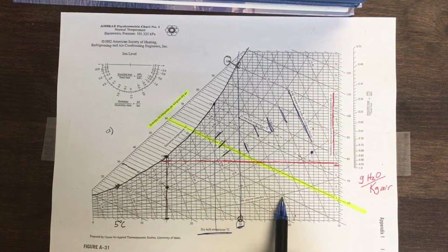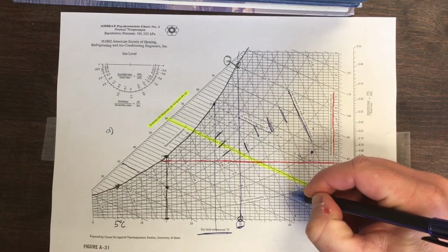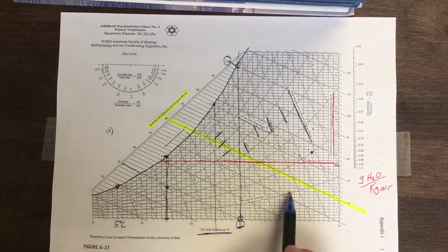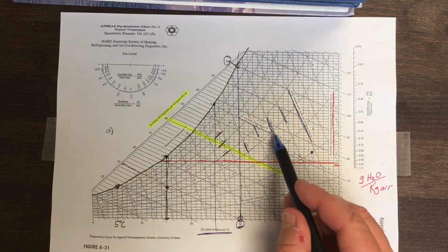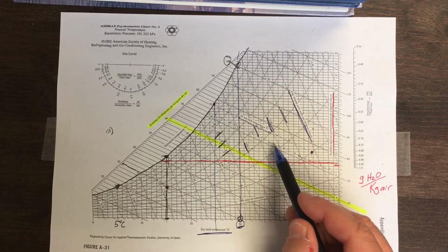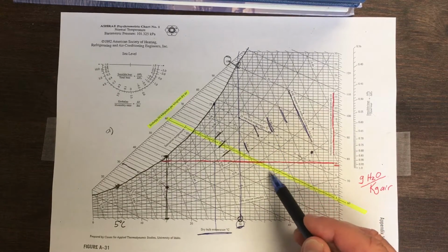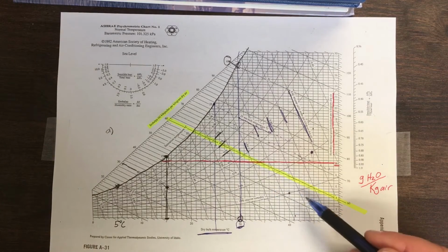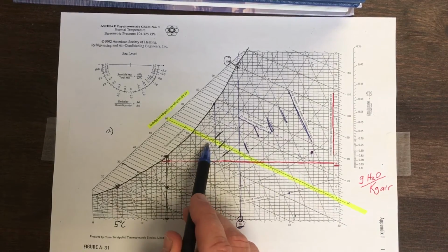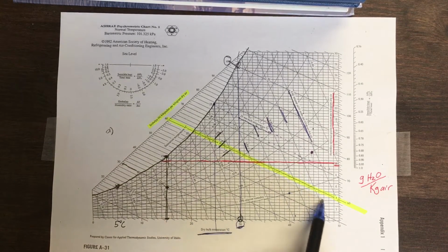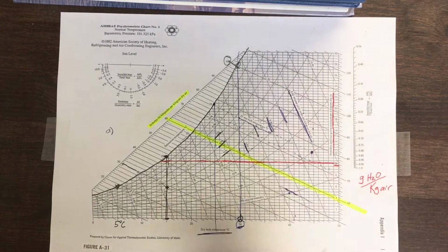Say it's 10% relative humidity, 40 degrees C, which is about 100 Fahrenheit. As that water evaporates, we're on, let's see, here's 20, 25, 24, 23, 22, 21, 20, 19. We're about 19 degrees C. So here's 20, I've kind of written over it, but that's the wet bulb temperature of 20. There's the wet bulb temperature of 19. So we would have a wet bulb temperature less than 19 degrees C. That's in the 60s Fahrenheit.